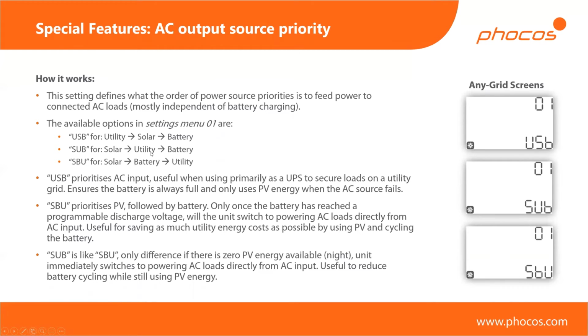Only if those two are not sufficient, and it's up to you, there's a parameter setting where you can decide how far you want to discharge your battery before this happens. But at some point, if you're producing less energy than you're consuming between solar and utility power, it will automatically switch over to battery, or basically as soon as the grid fails, it will automatically switch over to battery mode. Then it will simply discharge your battery as long as it can to provide power to your loads. Of course, if in the meantime you have enough PV coming in again, PV will increase the battery voltage again to keep your battery topped up. This middle scenario, I think, is most useful for Western countries where you have a more or less stable grid, but your priority is to save power on your utility bill, and maybe you don't want to cycle your battery, because you're reducing the cycling on your battery.